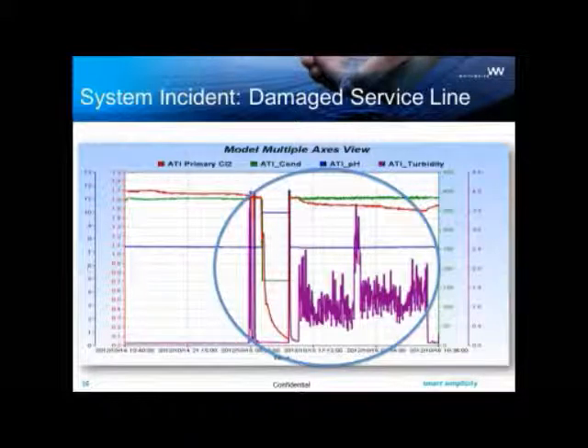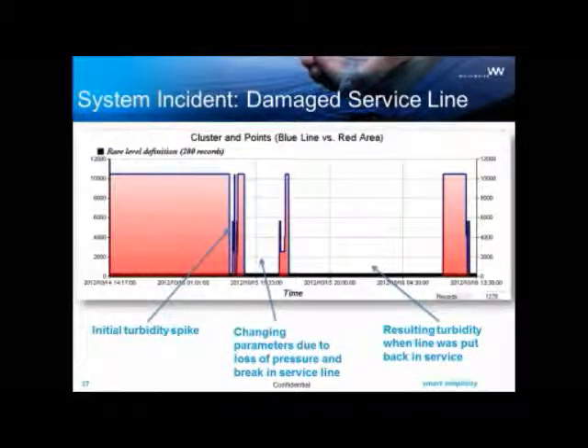Okay, here we have a system incident of a damaged service line, where you can see again the turbidity going crazy, and the free chlorine. From the statistical point of view, you can see the initial turbidity spike on the left side, the changing of the parameters due to the loss of pressure and the break in the service line, and then the resulting turbidity when the line was put back in service. So this is a very important tool to understand that everything is back to normal, and not only alerting about an event.